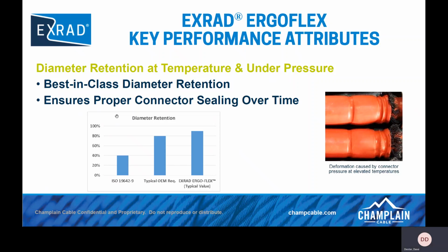ISO 19642 defined a test and minimum standard of 40% retention of original diameter. Now, this is a pretty low bar, allowing up to 60% deformation. As such, OEMs typically require retention in the 80% range, and Ergoflex typically performs in the industry-leading 90% range. On the right, you can see deformation caused by the connector pressure. Some deformation is okay, but too much will not allow a passing result.